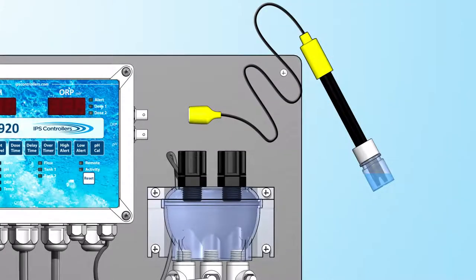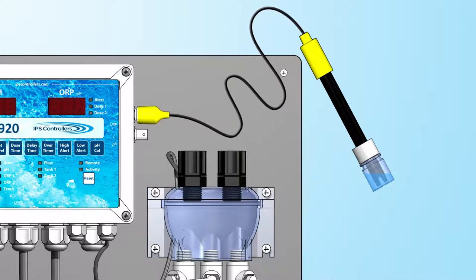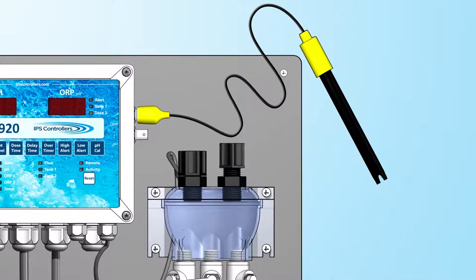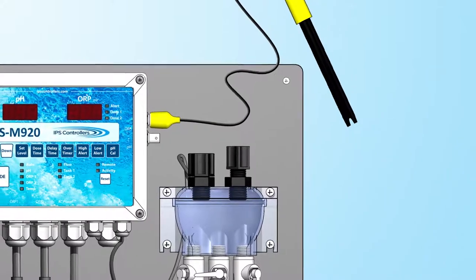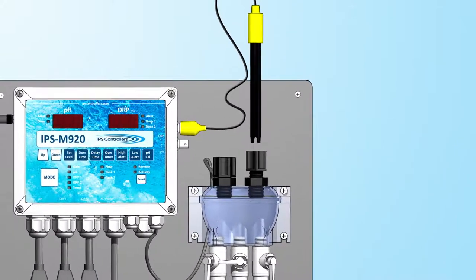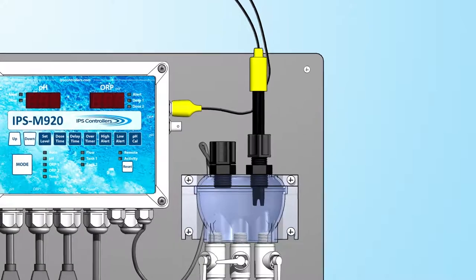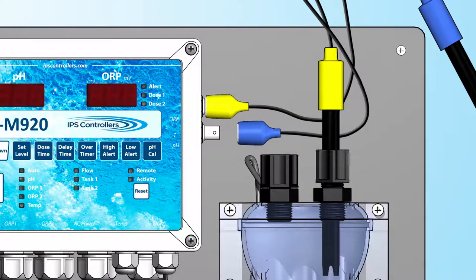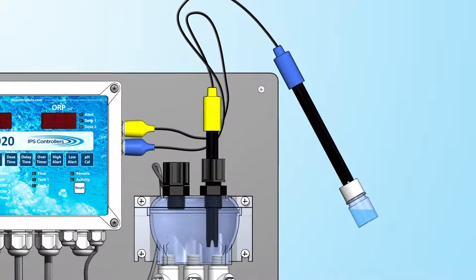To install the sensors, starting with the ORP sensor, plug the cable into the BNC connector on the controller, labeled ORP. Remove the protective bottle from the end of the sensor and set it aside for winterizing. Loosen one of the compression fittings on the top of the flow cell. Carefully insert the sensor to about one half inch from the bottom of the flow cell interior. Hand tighten the connector. Repeat the previous steps to connect the pH sensor.